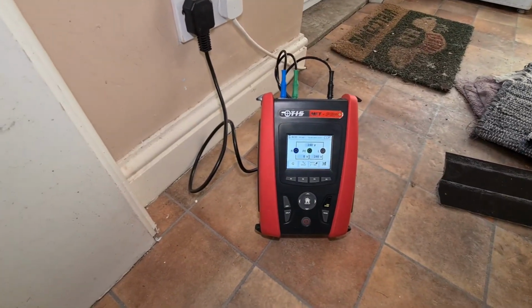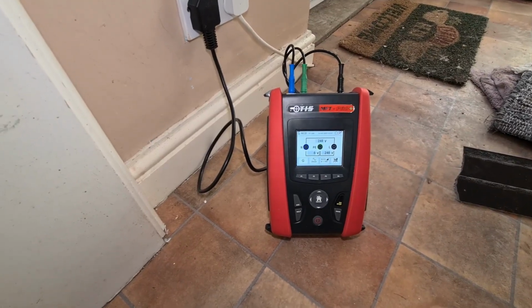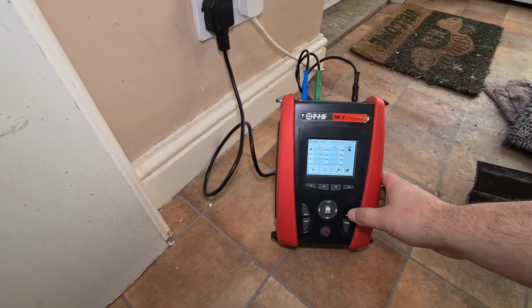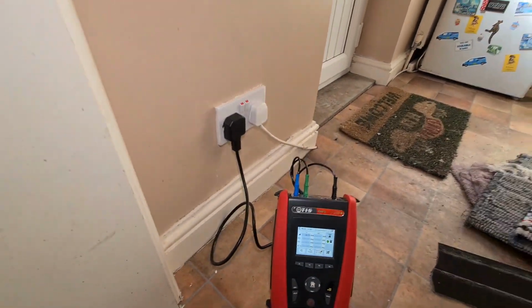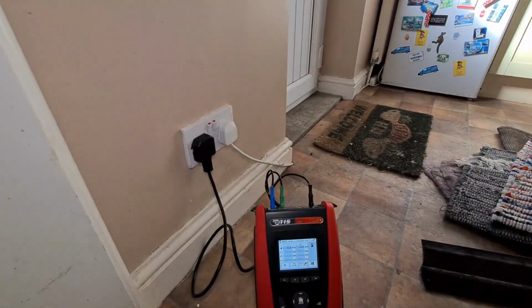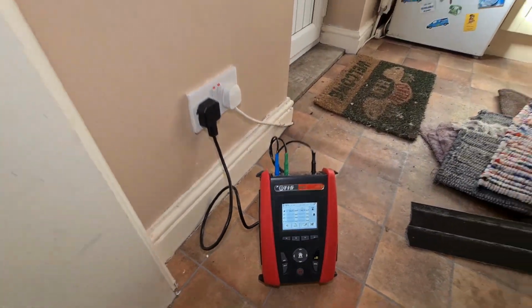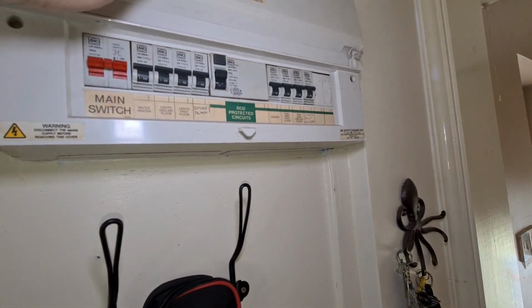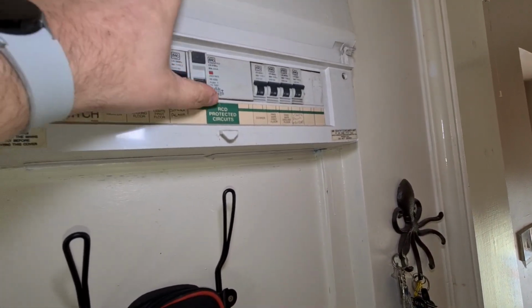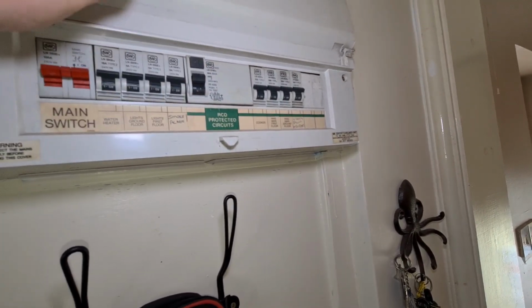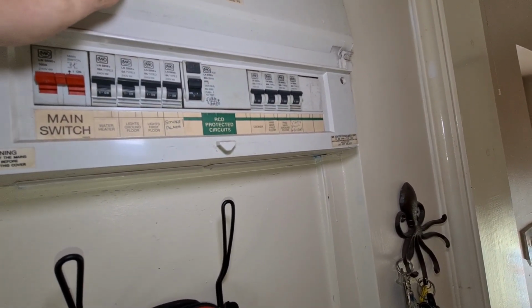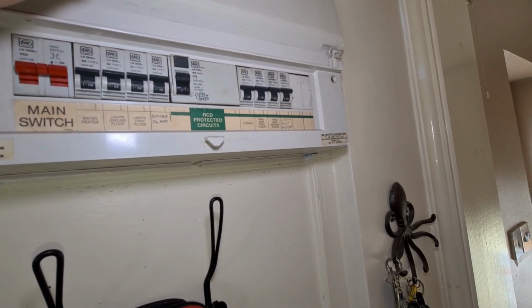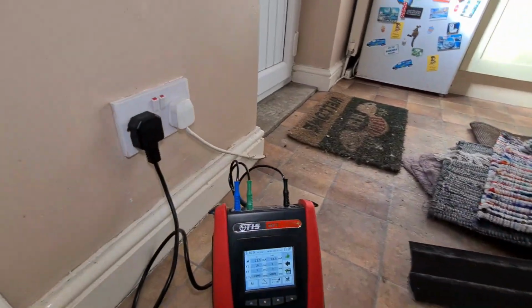So we can do some RCD testing now. You'll see I've got it all set up down there. We're all good to go in the auto mode. If I hit the test button, you'll see it starts to do its ramp, and we've got 22 milliseconds. That's one test in the 0 degree phase. Same again at 180. We'll just stay up here. You can see how quick and easy this is.